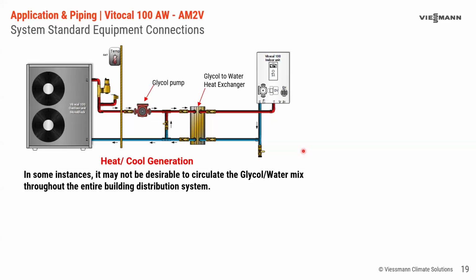So this is the option you can do. You could put a heat exchanger in here, which is a glycol to water, and I'm showing a flat plate heat exchanger here, but any kind. This is probably the most common version you're going to see, but a bundled heat exchanger, a tube and tube, or tube and shell, or something like that would work as well. But this is a flat plate, which means that on this side we have water, and on this side we have glycol. Now, there are a couple of things we want to look at for this.